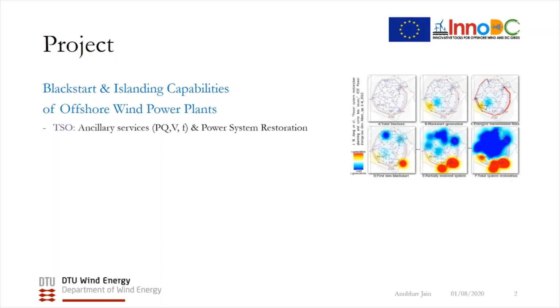Currently, wind turbines are no longer just passive units that connect to the grid, but are also required to support the grid during contingencies, especially because more and more renewable integration is pushing the dynamic stability limits of the existing grid system. Wind power plants provide ancillary services like real power control, reactive power control, and power factor control with ramp rate constraints, but more advanced services like reactive current injection are being demanded by new grid codes for low voltage ride-through and reactive power stability.